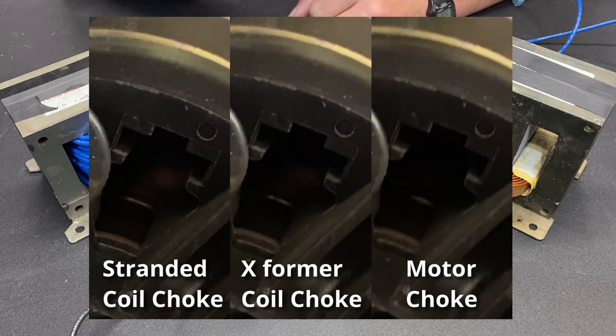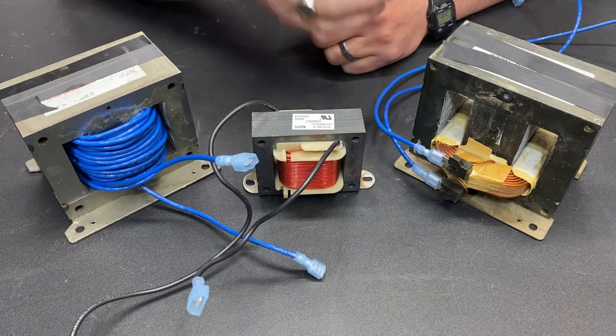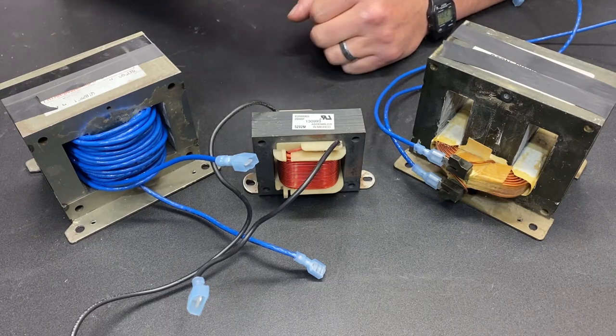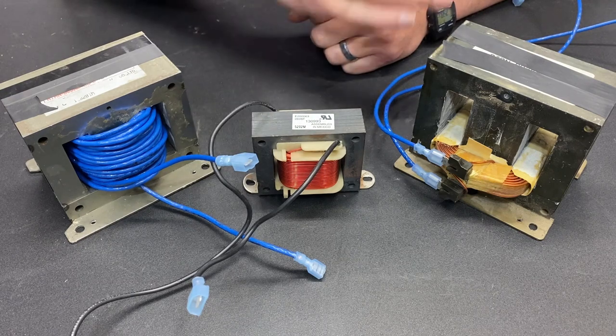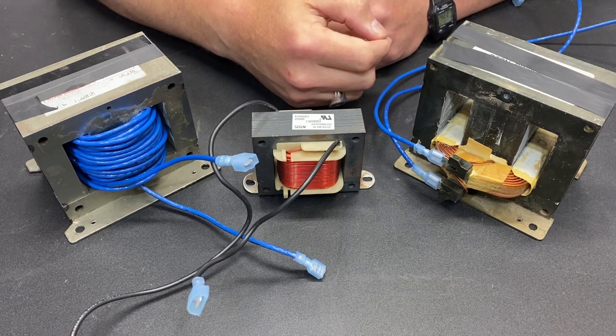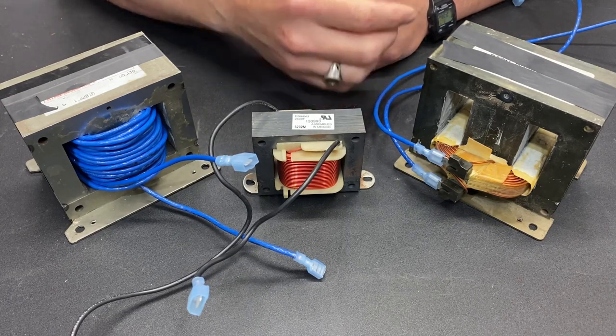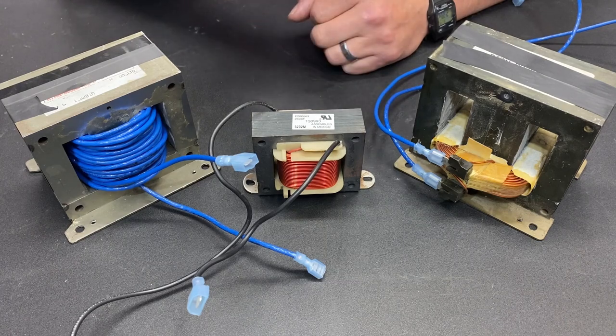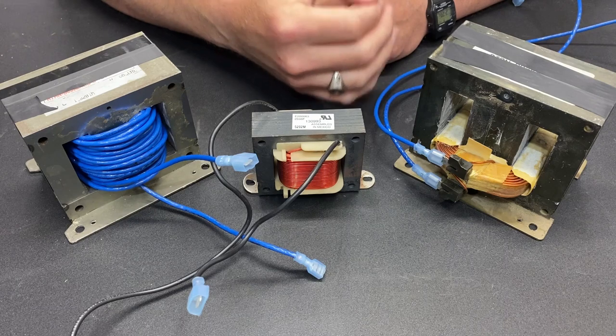This is why a choke is so important. If you are not running a choke, that constant sparking is going to significantly decrease the life of that motor. It's no wonder that you hear people complain about an SCR voltage controller burning out their motor, because without a choke, you're going to get lots of that sparking and the days of your motor's life are numbered.